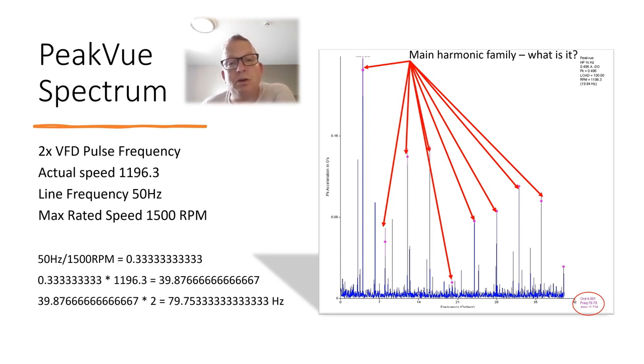So what we've got to keep an eye out for is the electrical firing frequency, two times the pulse frequency, which can be noisy on some motors, especially if it's not got the best cables installed. So 50 divided by 1500 gives us 0.3333 recurring, times that by the actual speed, and times by two because we've got north and south, gives us 79.75 hertz, which is this frequency here.